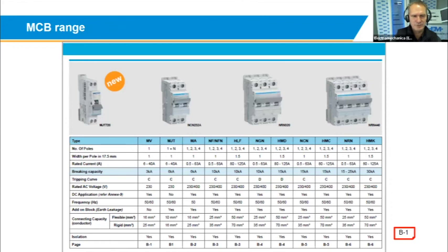For the ease of use and to try and assist our customers when selecting miniature circuit breakers, we actually added this table here, to try and make it easier for you to select a product. So if you want to look for a 10kA product, you can see 10kA. Which do you want? Do you want a D curve? Do you want a C curve? No, I want a C curve. Okay, then you can look between these two. What current rating are you looking for? Up to 63 amp, you go for this range. And for 80 to 125 amp, you go for the HLF range. And then it will also guide you to the catalog page. So you'll find this on page B3.